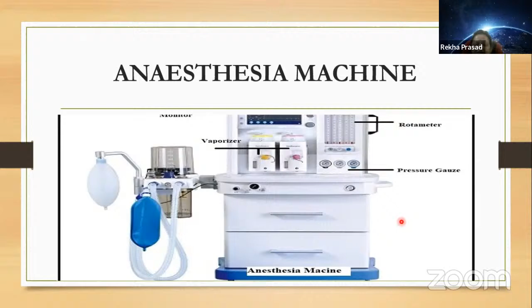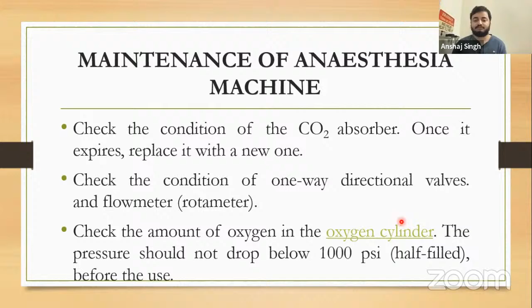Maintenance of anesthesia machine. Check the condition of the carbon dioxide absorber. Once it expires, replace it with a new one. Check the condition of one-way directional valves and flow meter. Check the amount of oxygen in the oxygen cylinder. The pressure should not drop below 1000 psi before the use.